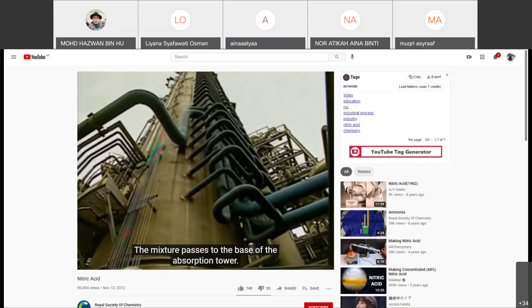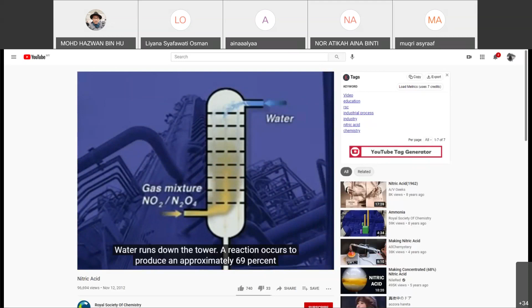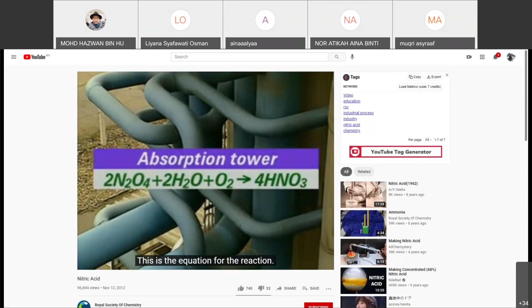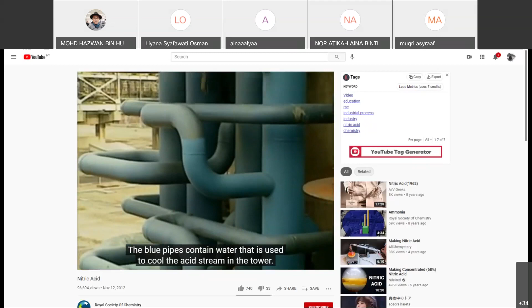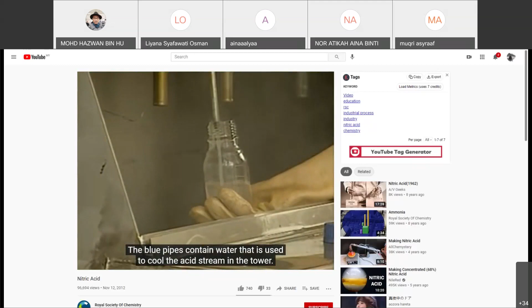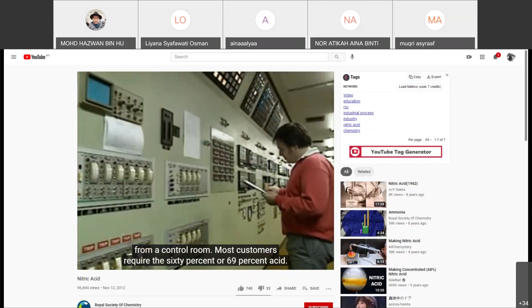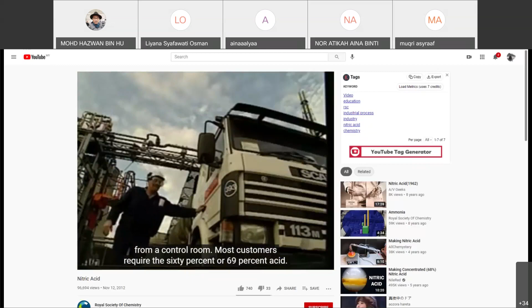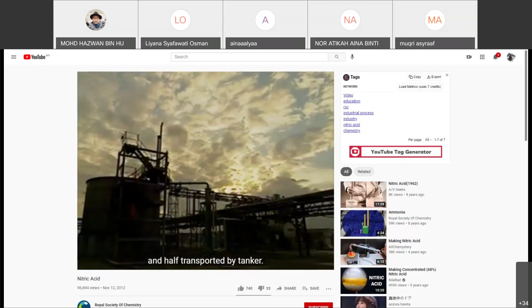The mixture passes to the base of the absorption tower. The gases rise up the tower and through a series of slotted trays. Water runs down the tower. A reaction occurs to produce an approximately 69% solution of nitric acid. This is the equation for the reaction. The reaction is exothermic. It produces heat. The blue pipes contain water that is used to cool the acid stream in the tower. The production process is monitored and controlled remotely from the control room. Most customers require the 60% or 69% acid. About half the nitric acid is used on site and half transported by tanker.